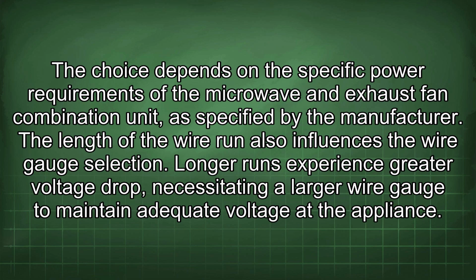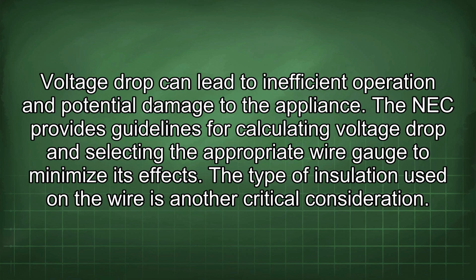Longer runs experience greater voltage drop, necessitating a larger wire gauge to maintain adequate voltage at the appliance. Voltage drop can lead to inefficient operation and potential damage to the appliance. The NEC provides guidelines for calculating voltage drop and selecting the appropriate wire gauge to minimize its effects.